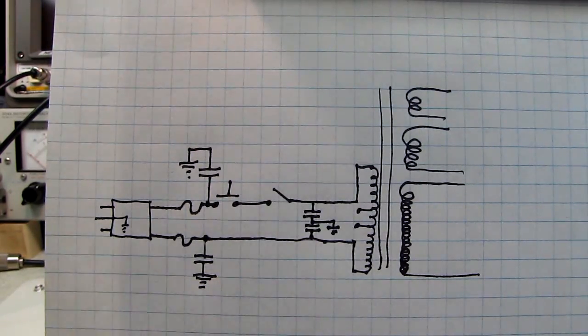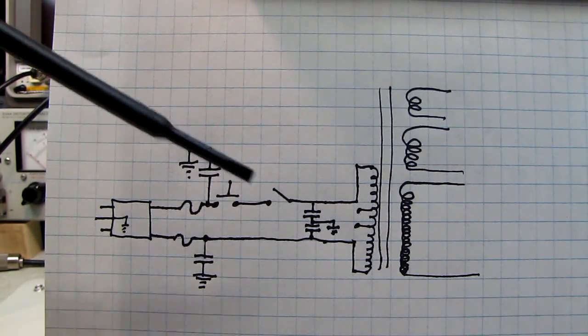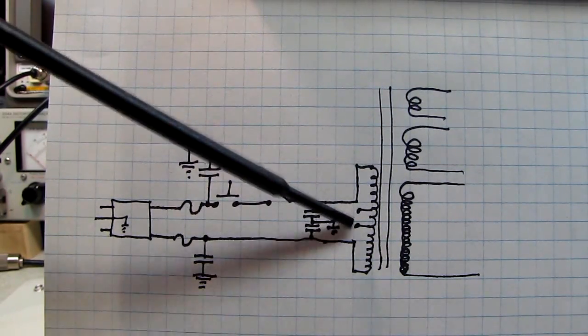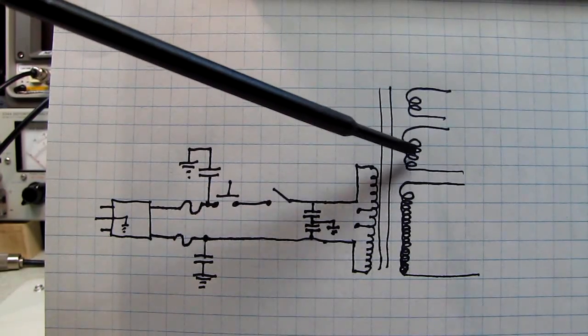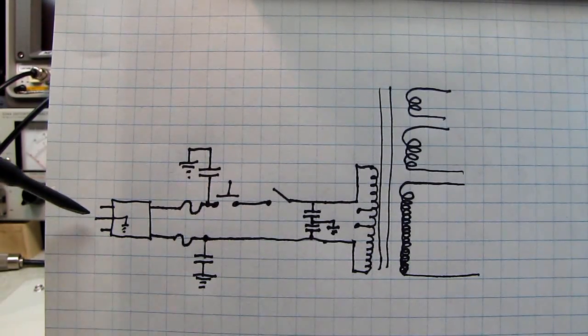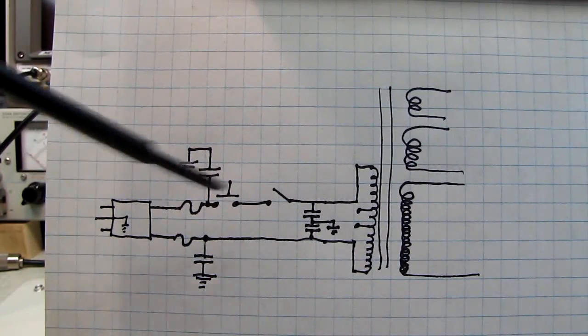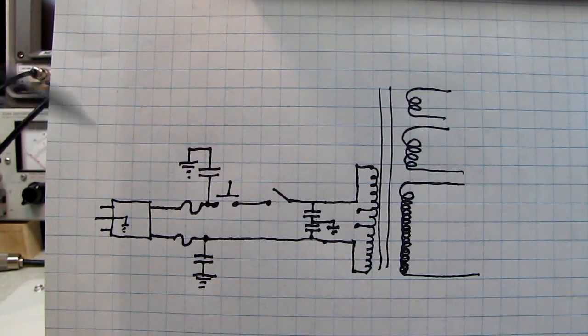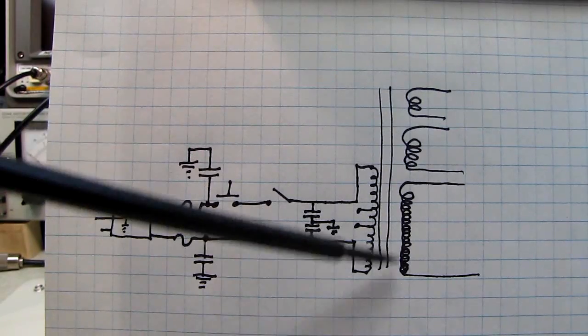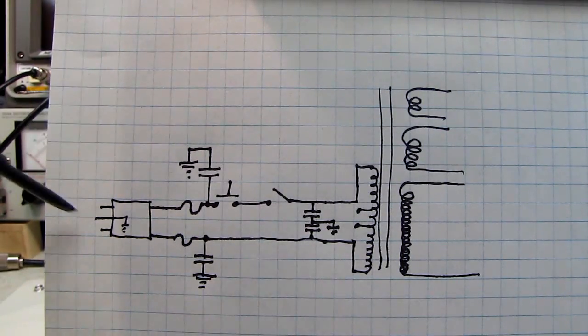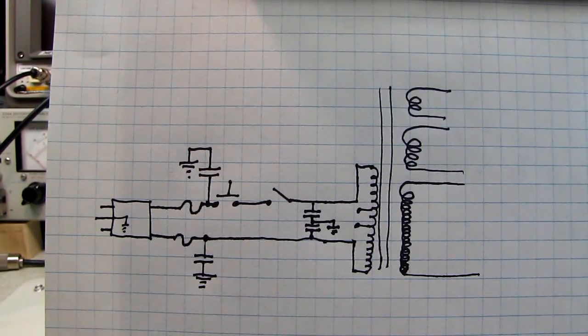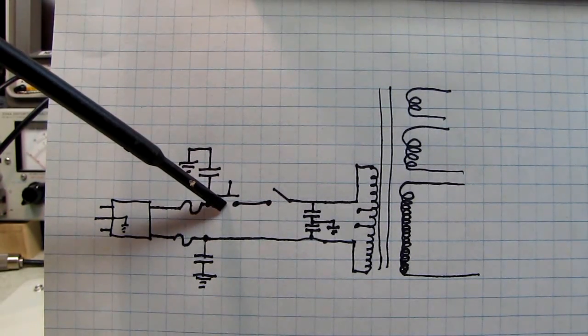Now, these are just drawn in, but one of these is going to be a winding for the 12 volt power supply. If it's running on 220 volts, the transformer's tapped for 220, we should be getting 12 volts out. Likewise, if one leg is open and we're referencing to ground, we're going to have 110 volts if the circuit's coming through the primary and here to ground using one leg. And that would account for the roughly 6 volts on the panel lamps being on and the fact that the fan's running. What is curious is this switch is always closed when the cover's on the unit.